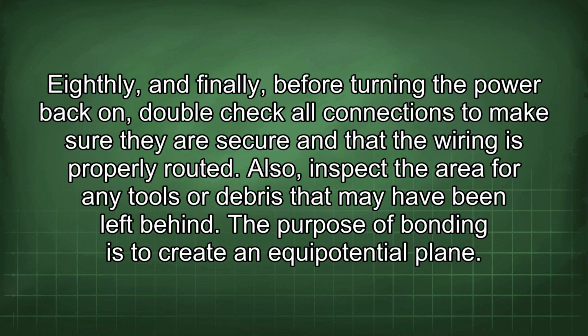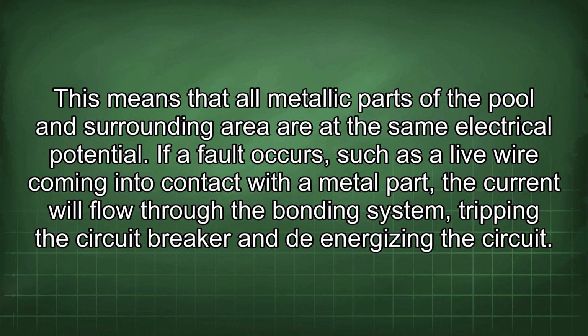Eighthly, and finally, before turning the power back on, double-check all connections to make sure they are secure and that the wiring is properly routed. Also, inspect the area for any tools or debris that may have been left behind. The purpose of bonding is to create an equipotential plane. This means that all metallic parts of the pool and surrounding area are at the same electrical potential. If a fault occurs, such as a live wire coming into contact with a metal part, the current will flow through the bonding system, tripping the circuit breaker and de-energizing the circuit.